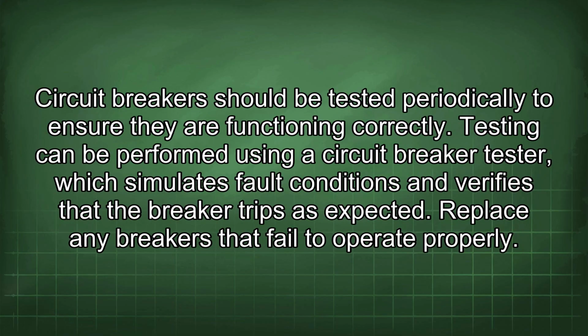Circuit breakers should be tested periodically to ensure they are functioning correctly. Testing can be performed using a circuit breaker tester, which simulates fault conditions and verifies that the breaker trips as expected. Replace any breakers that fail to operate properly.